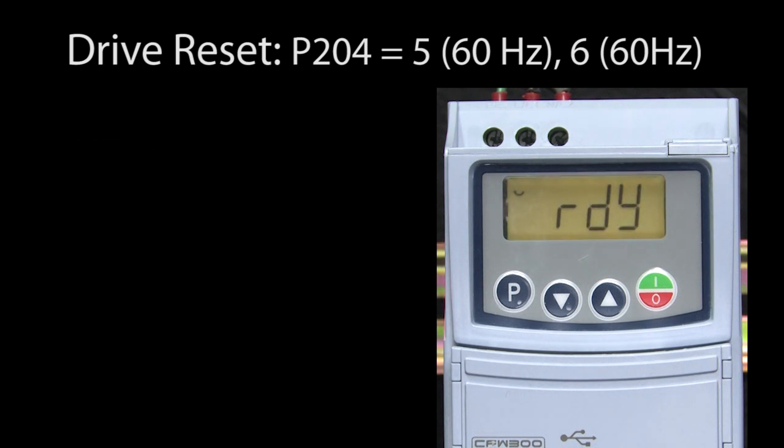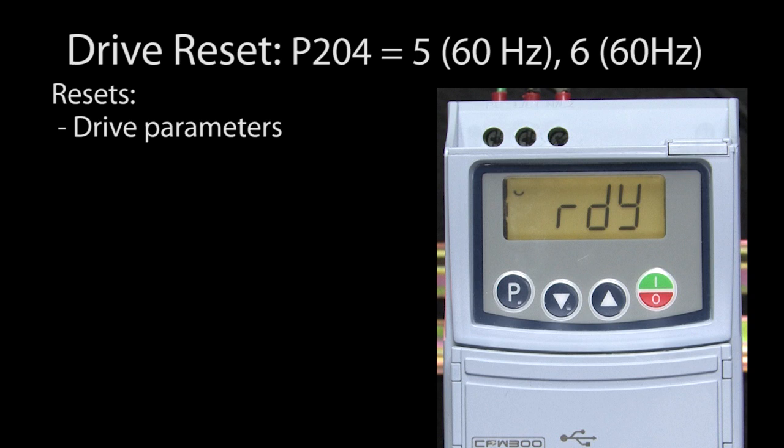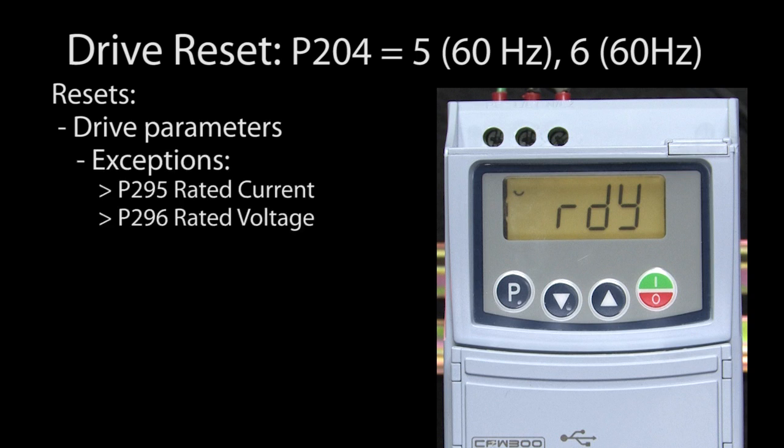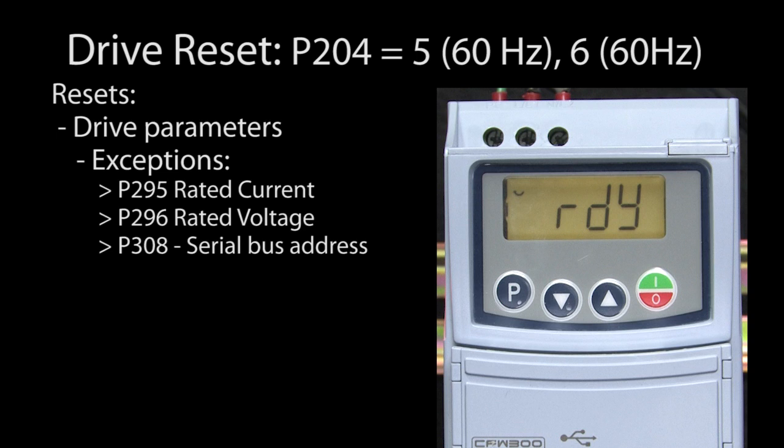That reset all of the drive parameters to factory default except for the drive's rated current, rated line voltage, and the serial address. That's good to know because you'll still be able to communicate with the drive after a reset, assuming you are using the default comm channel parameters.